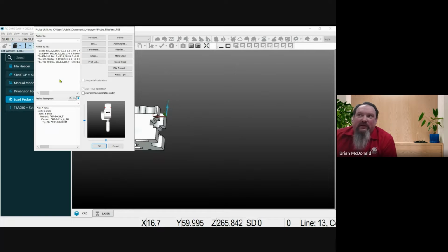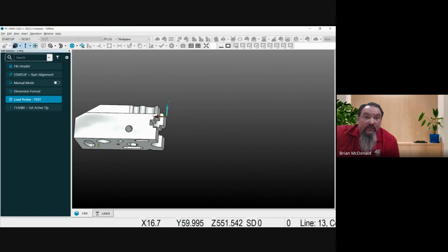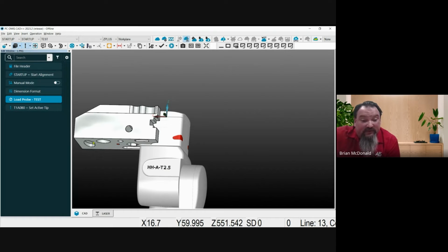So if it's going to run into the cal rack, that's not in that file that it's grabbing. So that was the problem with that. That does only look for the legs and the table as it spins around and does its calibration. And that covers about everything under what I had for probe calibration.